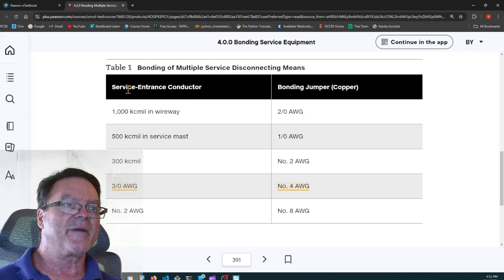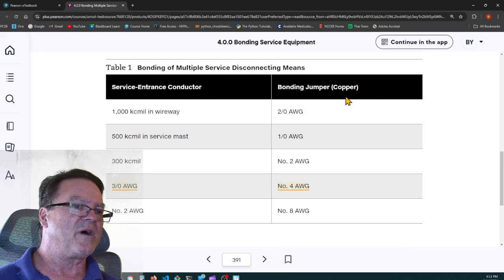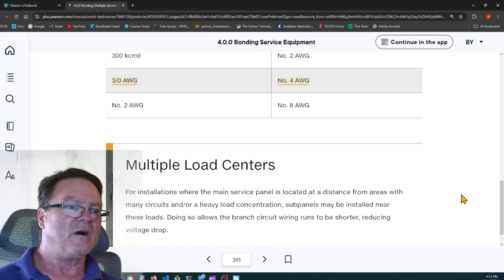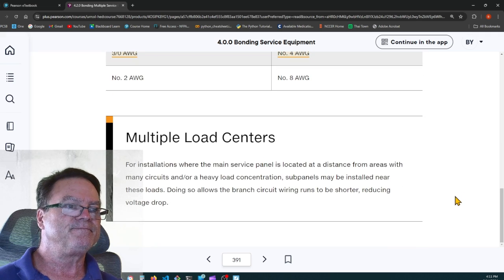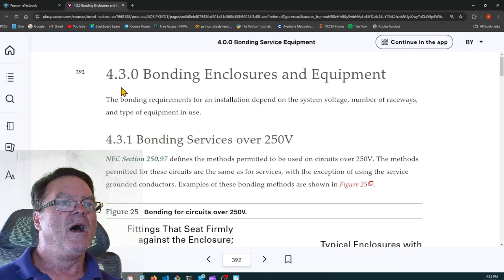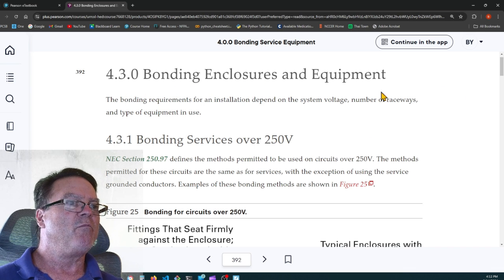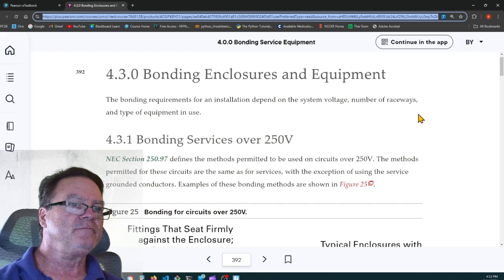So here's a highlight. They're talking about the service entrance conductors and what size bonding jumper. For a 3-aught ungrounded conductor, you need a number 4 gauge bonding jumper. All right.